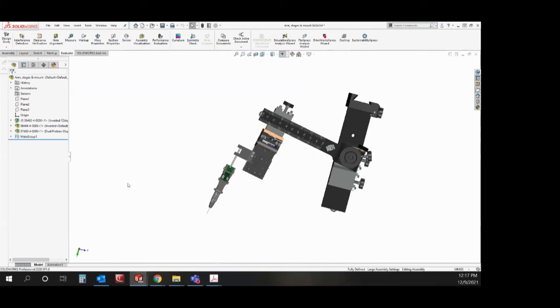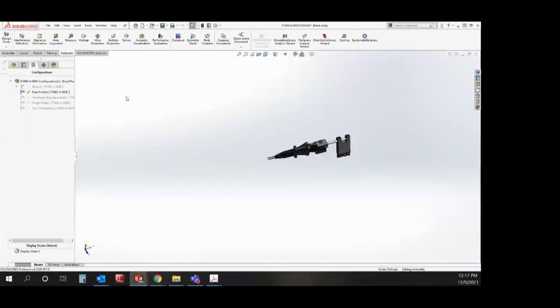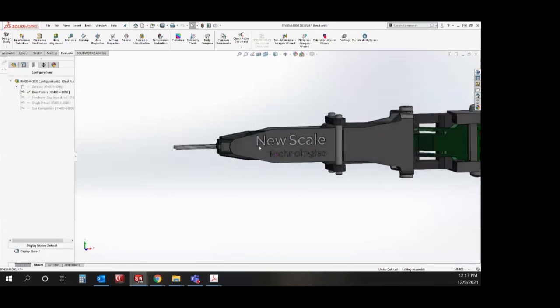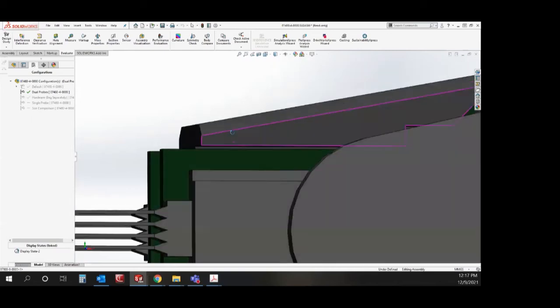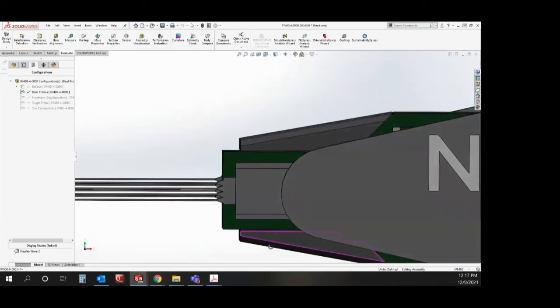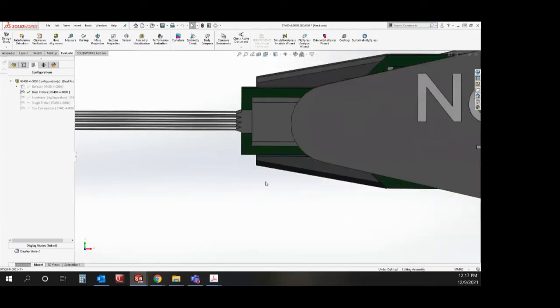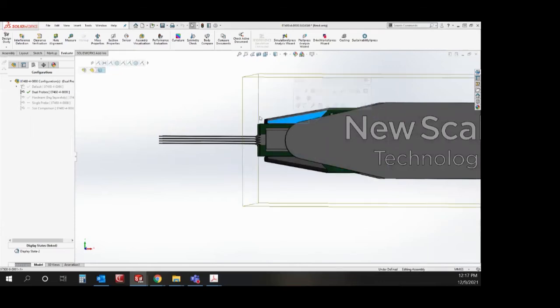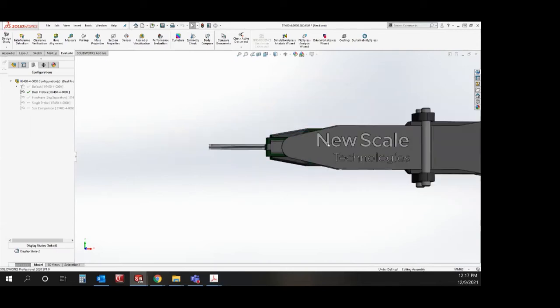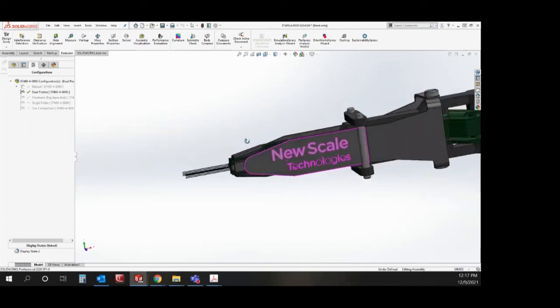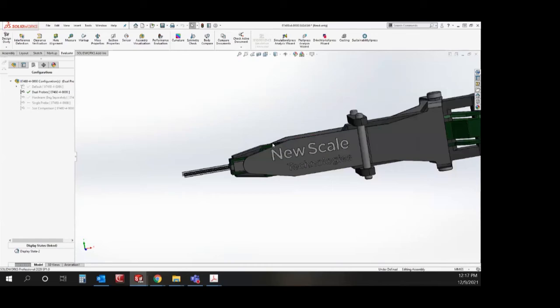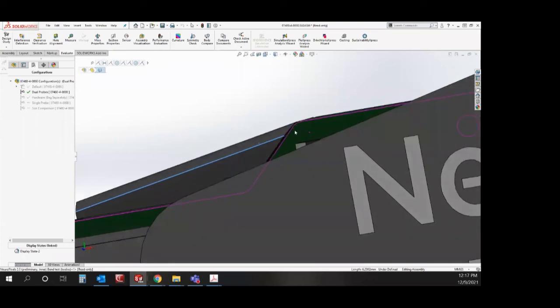There is room for adjustment within the probe mount locating features in the front. We do leave a little bit of space here to allow for adjusting in case of misalignments. And in the case of a misalignment, we would recommend that you put a little bit of adhesive between the probe PCB and the probe holder's body to keep it in place when you have it aligned. Something like a UV glue that can be easily removed should you need to replace the probe. We'll have specific recommendations on that in the coming weeks, but we do keep these features here as close as possible to the features of the PCB to help keep it straight.